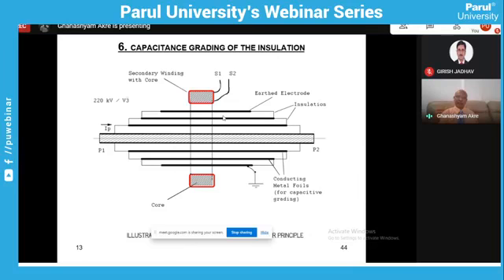So that is not economically or optimally used. That is why these voltages are divided into small fractions, and made to divide the voltage across all the sections and all the elements of the insulation. That is how you can reduce the diameter of the primary insulation. This is how the current transformer is generally done. This is the primary, this insulation is capacitively graded, and then you put the core here, tank, insulator, and top chamber for P1, P2, and it makes a transformer.